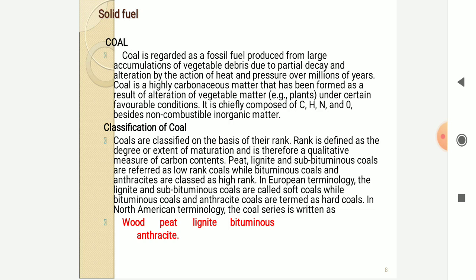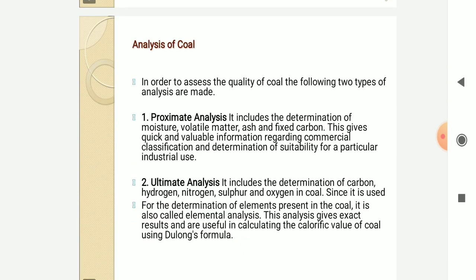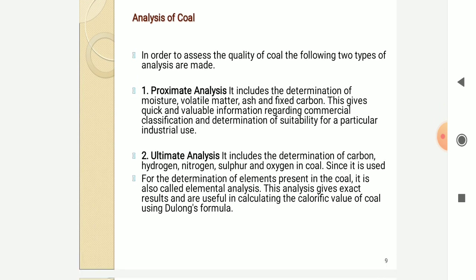In North American terminology, the coal series runs from peat. Some examples are wood, peat, lignite, bituminous, and anthracite. In order to assess the quality of coal, two types of analysis are done: proximate analysis and ultimate analysis. Proximate analysis includes the determination of moisture, volatile matter, ash, and fixed carbon, and gives quick valuable information regarding commercial classification and suitability for particular industrial use. Ultimate analysis includes the determination of carbon, hydrogen, nitrogen, sulfur, and oxygen in the coal, and since it determines the elements present, it is also called elemental analysis.